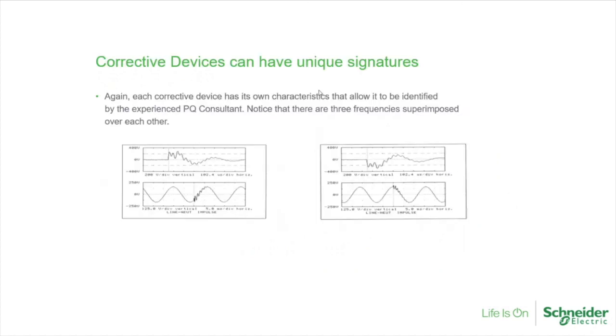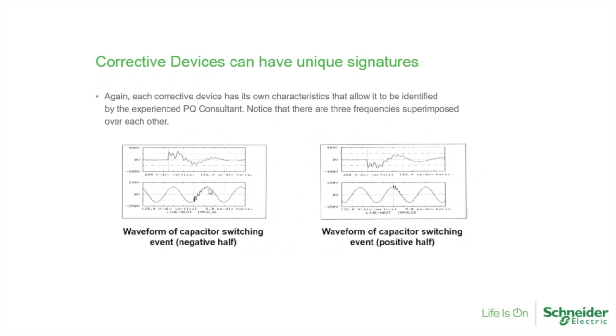And then corrective devices can have unique signatures. So this is an example of a cap bank being thrown in. A cap bank creates a sinusoidal transient, which can be roughly a quarter cycle. And you'll see in this example how it creates, more or less, a sine wave on the sine wave. And then also, analyzing cap banks, I know they're typically around the 13th harmonic, and then there's usually a couple of other harmonics that they inject. But when you gain this information, it can help you identify what caused the wave shape.